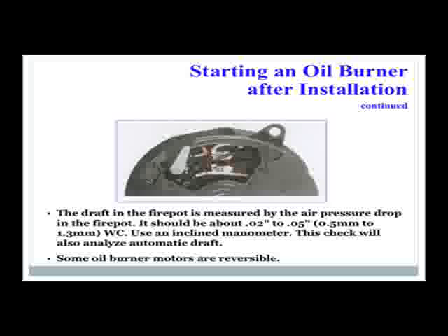The draft in the fire pot is measured by air pressure drop in the fire pot. It should be about 0.02 to 0.05 inches water column negative from the room pressure. In other words, it should be under the room pressure. Use an incline manometer. This check will also analyze automatic draft.